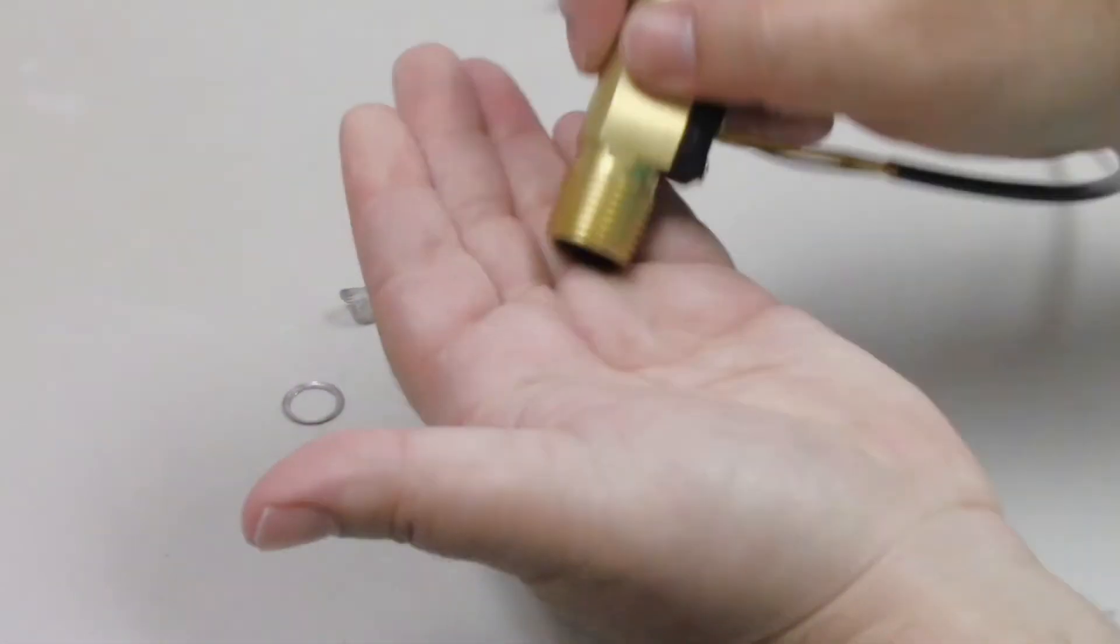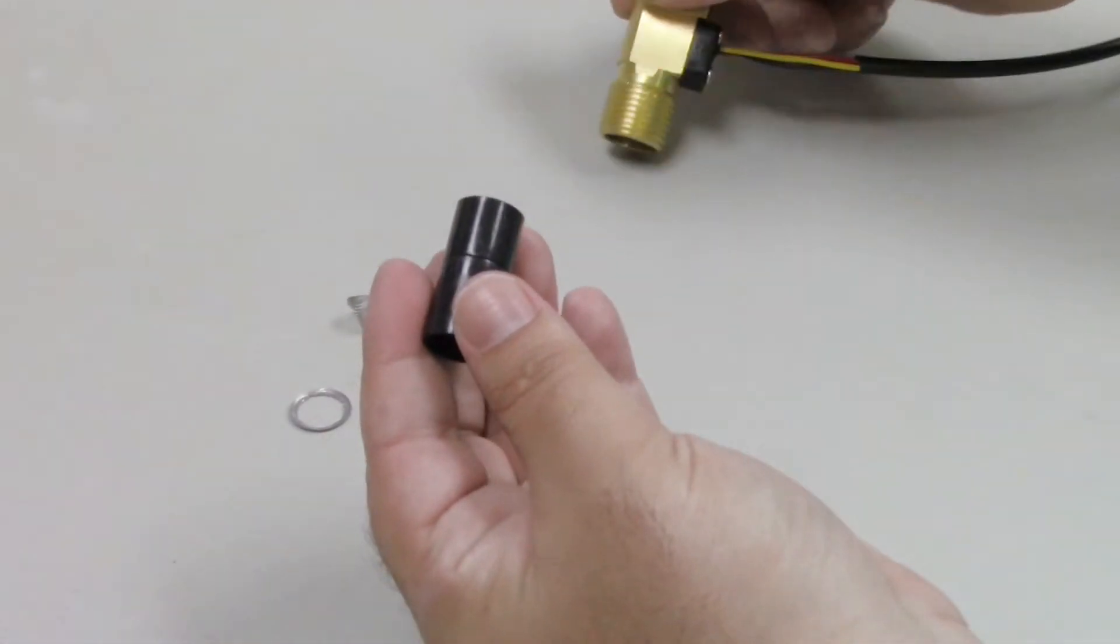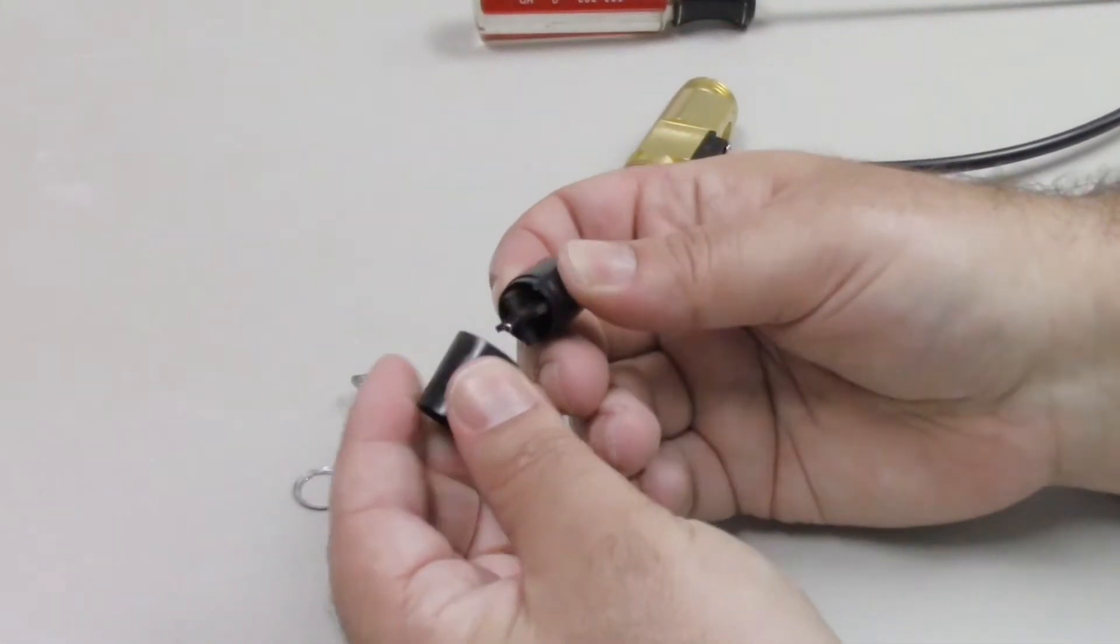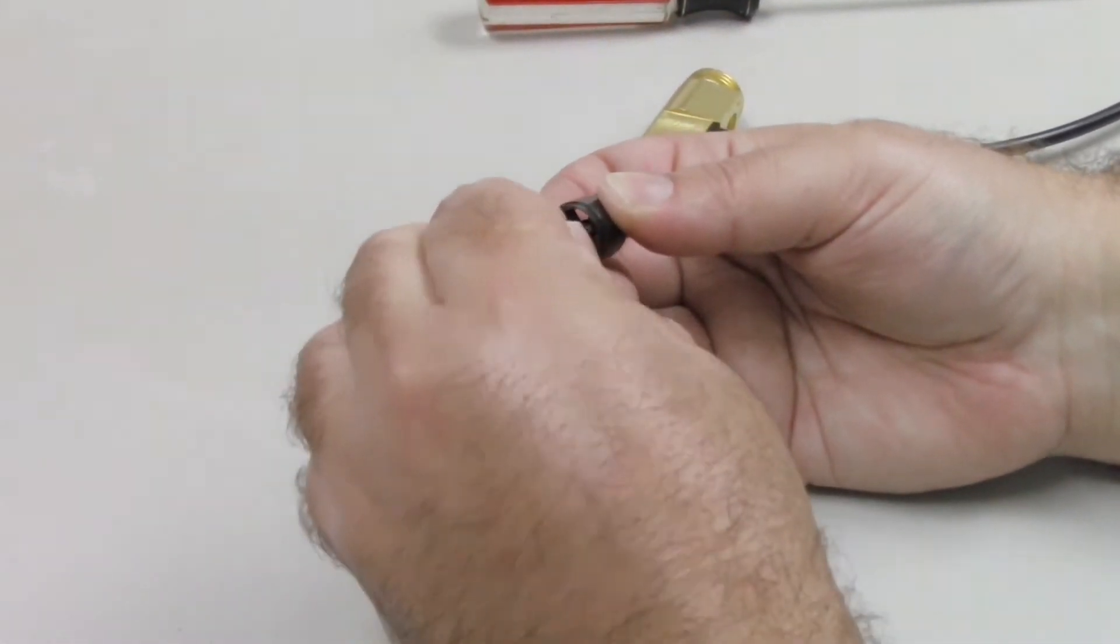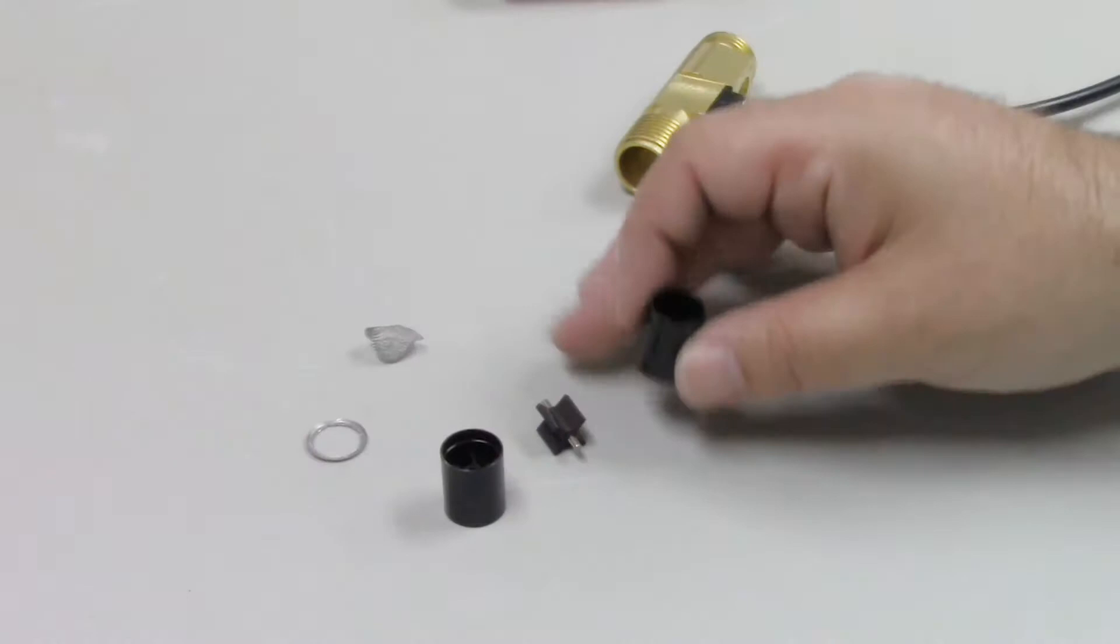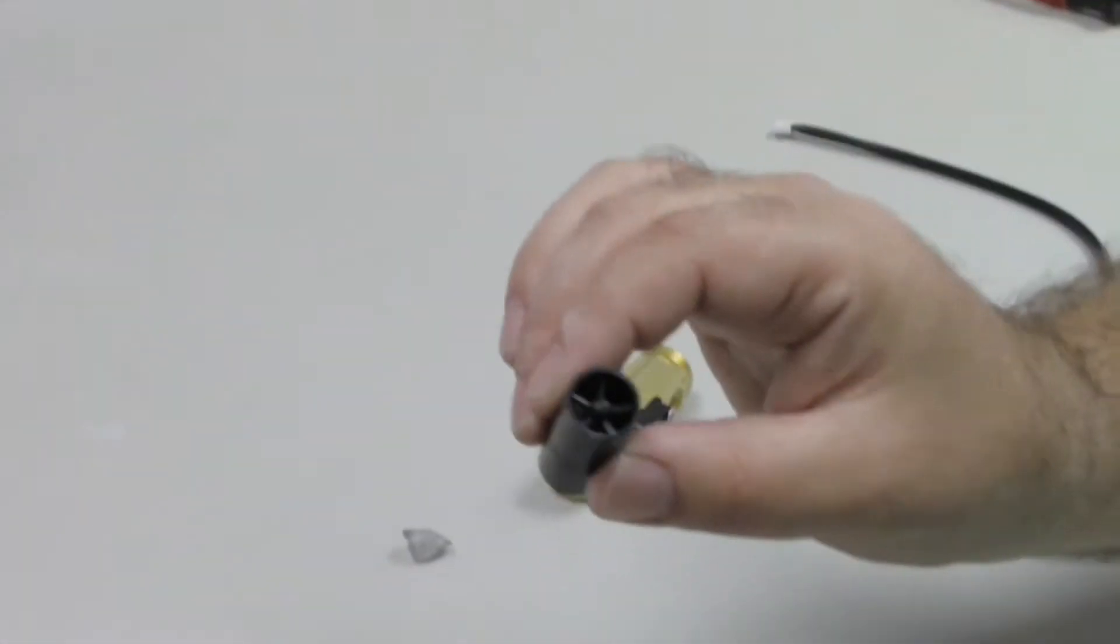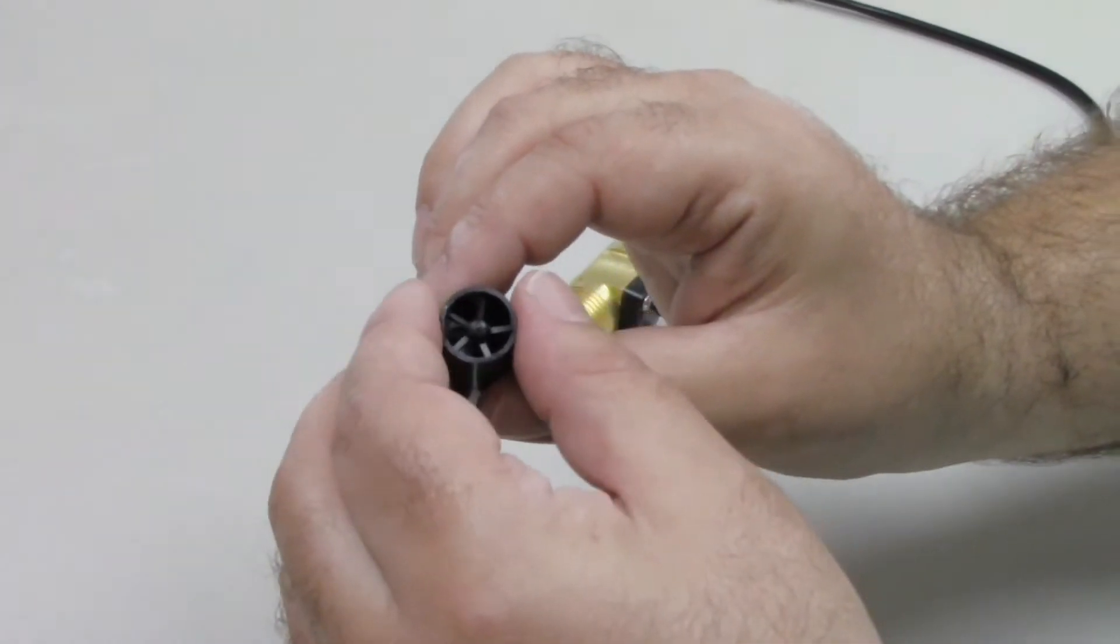Once the washer and mesh have been removed, we will remove the flow switch to check for any residue or buildup. After we check for residue, make sure the flow switch spins freely by blowing into the flow switch casing.